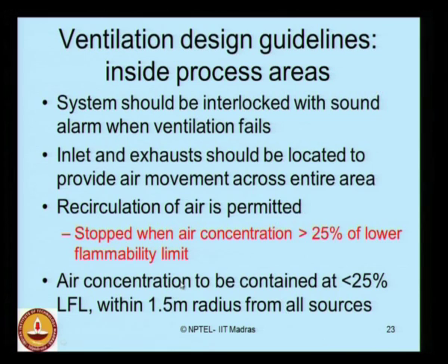The air concentration should be contained to be lower than 25% of the lower flammability limit of the fuel. Further, the air concentration should lie within 1.5 meter radius from all possible sources of ignition. So, it is what we call a contained environment.